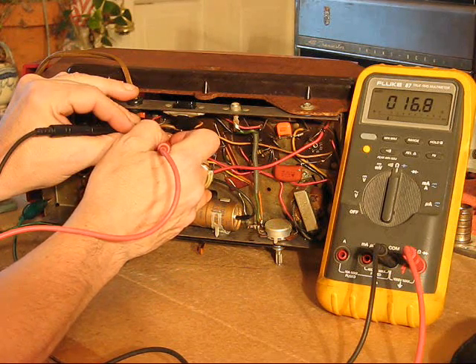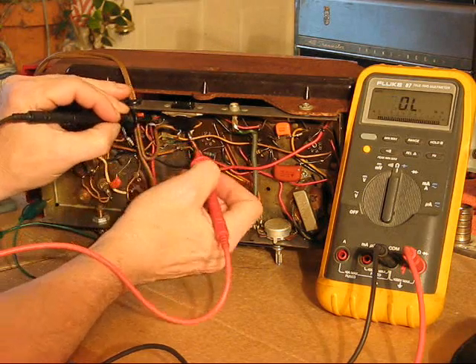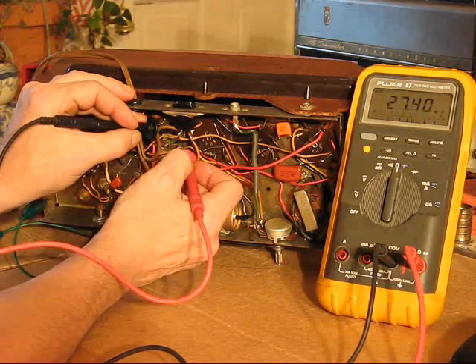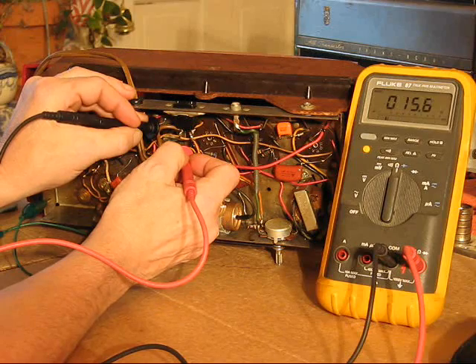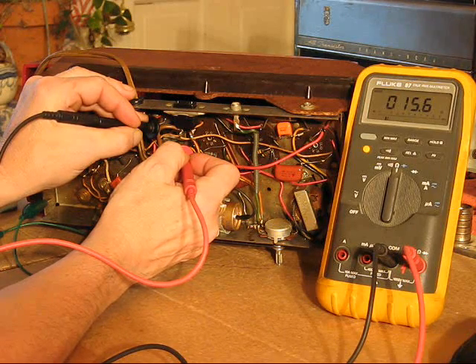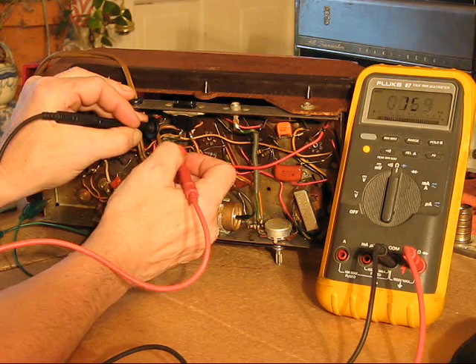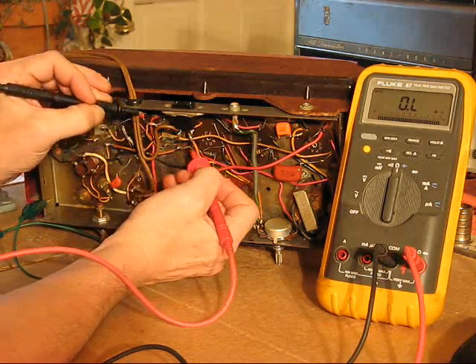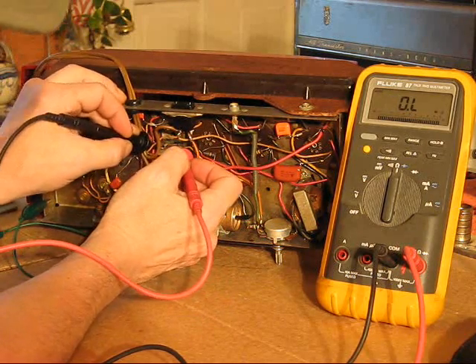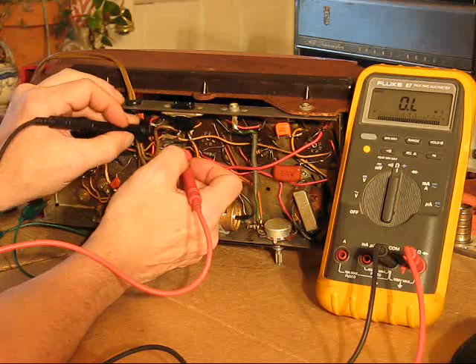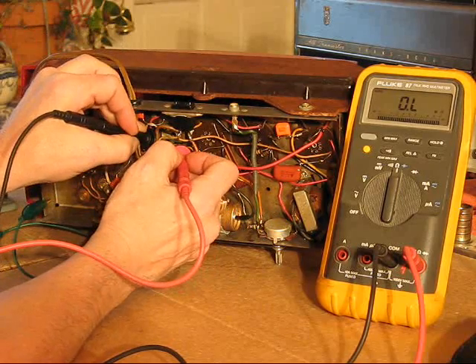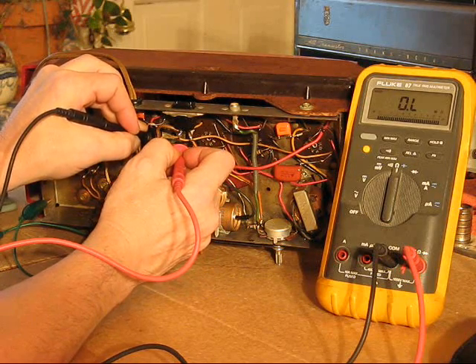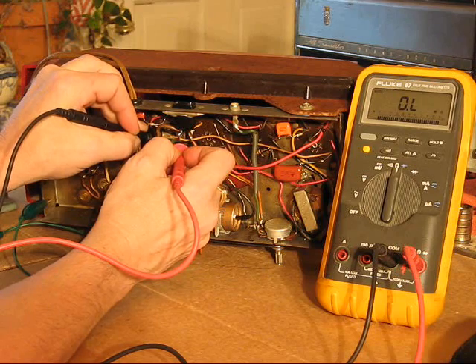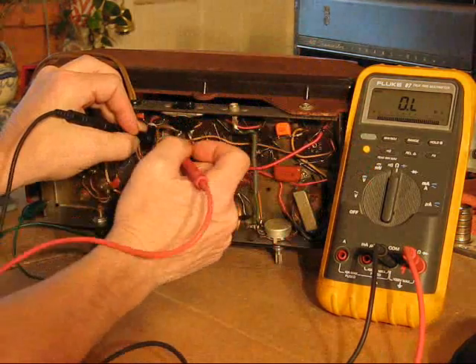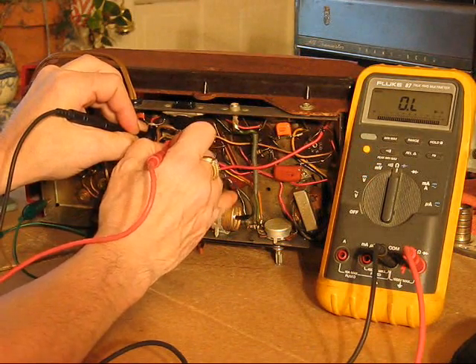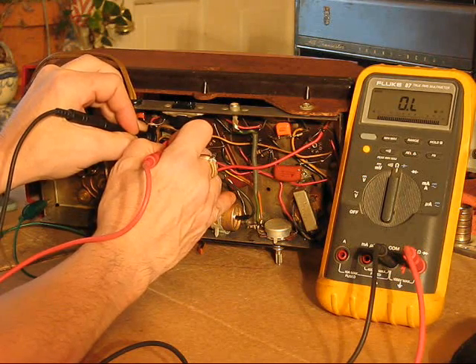Okay, 16, call it 17 ohms on one coil. 15.6 ohms on the other coil in this transformer. So primary, secondary both check good as far as continuity. Now let's see if there's any current flow between the windings. There isn't. Not at this voltage, which is somewhere probably well below 9 volts. Not surprising.